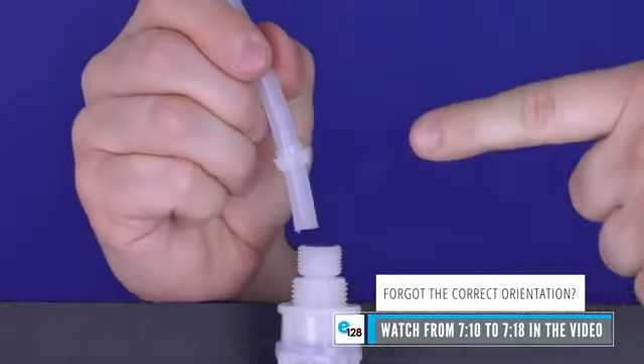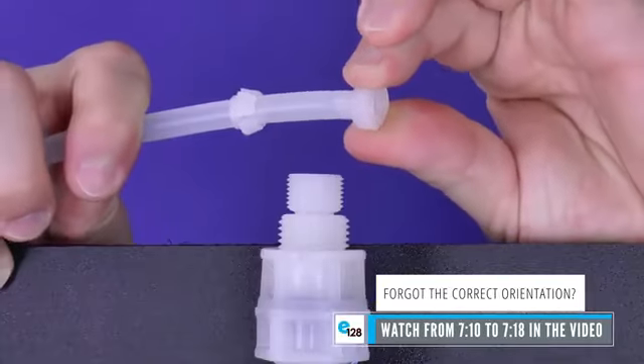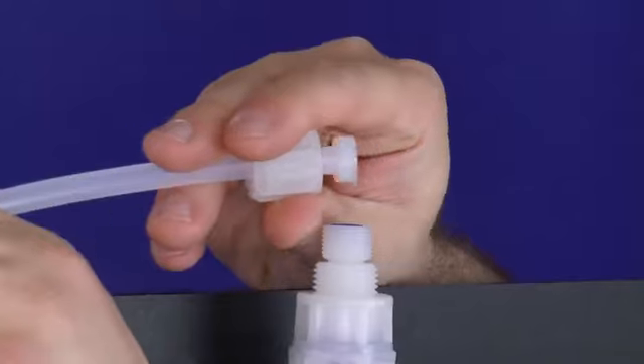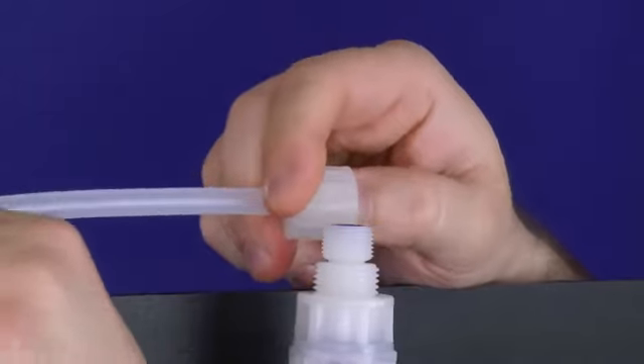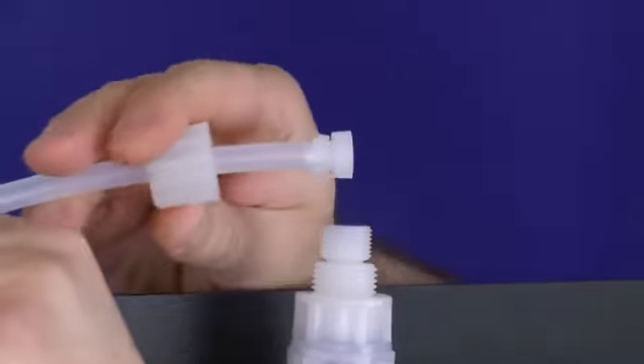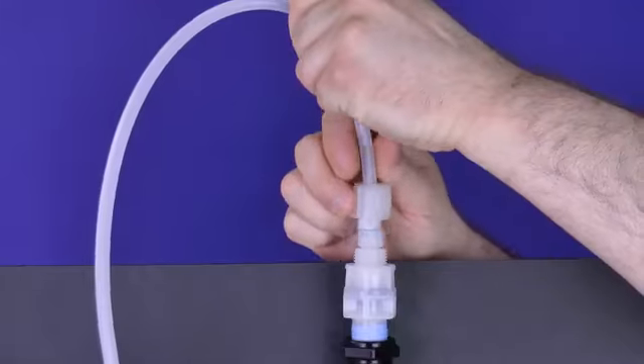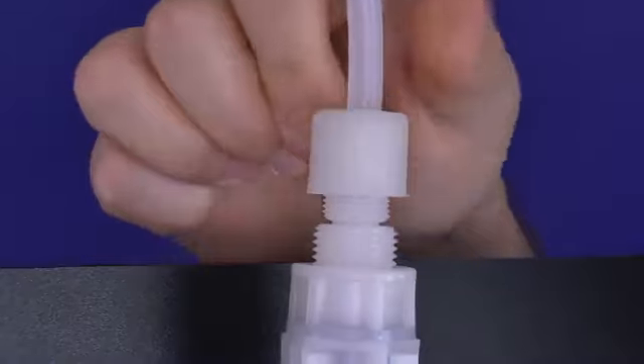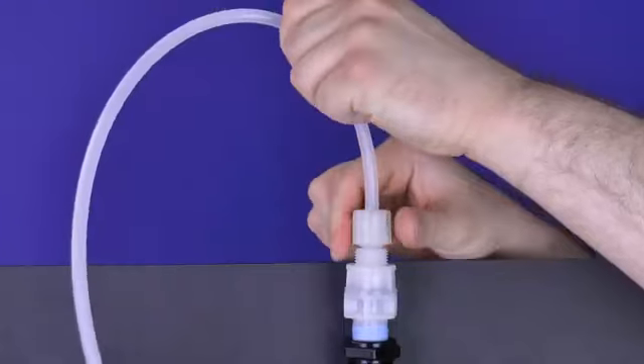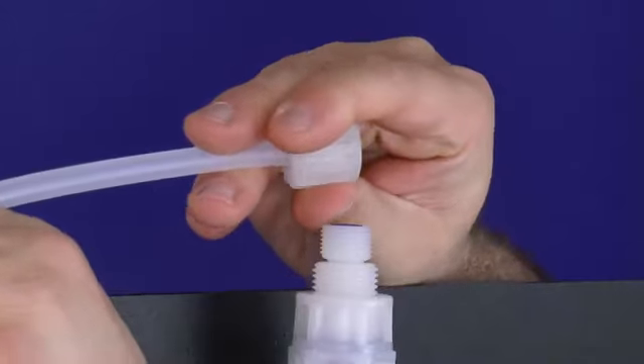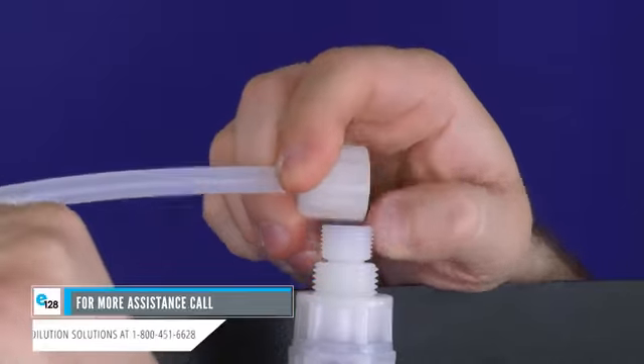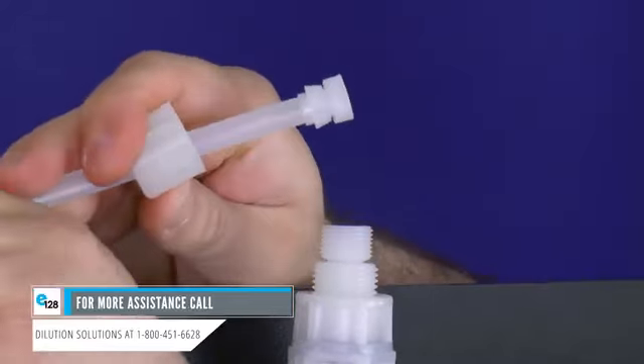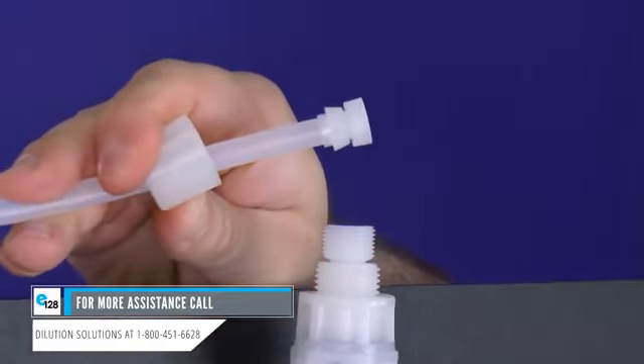Reattach the tube connections onto the loose end of the connected discharge tubing and be mindful of the orientation for the tubing connections. Pull the tube nut toward the nozzle to compress the collar and nozzle tight together, forming a ferrule connection. Reattach the tube and tube connections onto the injection valve by hand tightening the tube nut. Do not cross-thread nor over-tighten. If the tube nut is not securing, recheck the ferrule connection. Pull the tube nut toward the nozzle once more to compress the collar and nozzle together. Retighten the tube nut until secure.